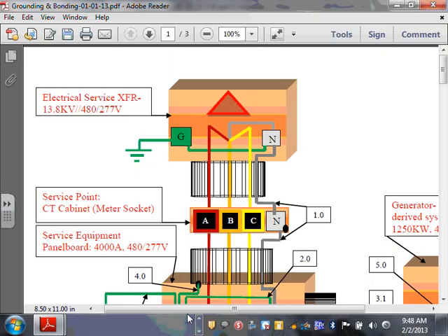So when we, as engineers or contractors, provide them with a load calculation for our hospital, they look at it and typically apply a service factor, a demand factor, between 50% and 70%. So if I ask for a 4,000 amp switchgear, the engineers will say, we know statistically that's not really what they want. We're going to apply a load factor of, say, 50%. So they give you a transformer worth 2,000 amp when you're asking for a 4,000 amp, or say a 3,000 amp worth, transformer.